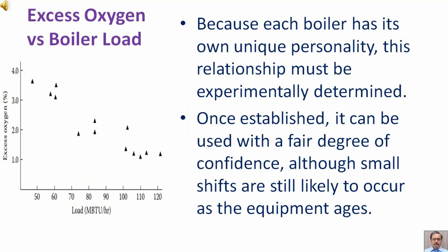Because each boiler has its own unique personality, this relationship must be experimentally determined. Once established, it can be used with a fair degree of confidence, although small shifts are still likely to occur as the equipment ages.